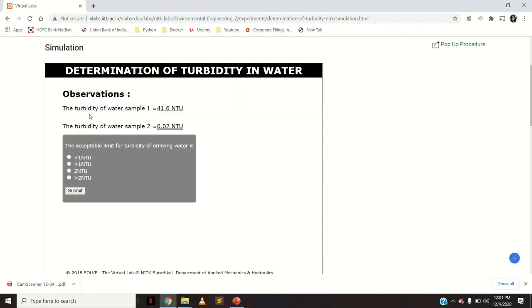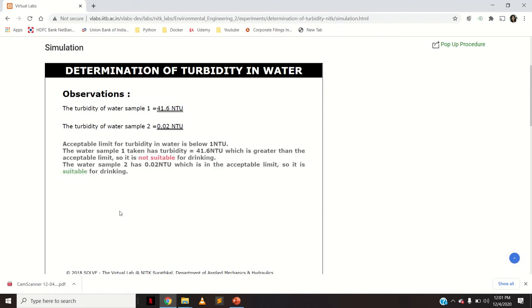The observations are: turbidity of the first sample was 41.6 NTU and turbidity of the second water sample was 0.02 NTU. The acceptable limit for turbidity of drinking water is less than 1 NTU. Since Sample 1 has turbidity of 41.6 NTU — greater than the acceptable limit — it is not suitable for drinking. Sample 2 at 0.02 NTU is within the acceptable limit and is suitable for drinking. Thank you so much.